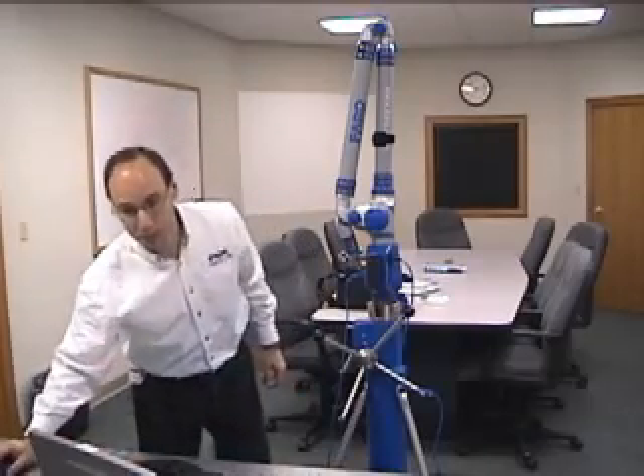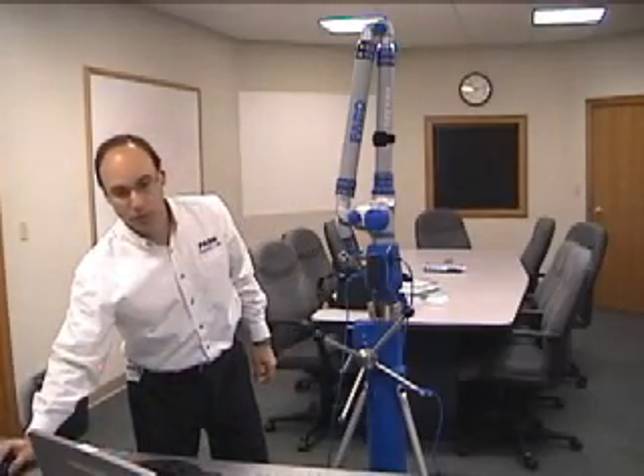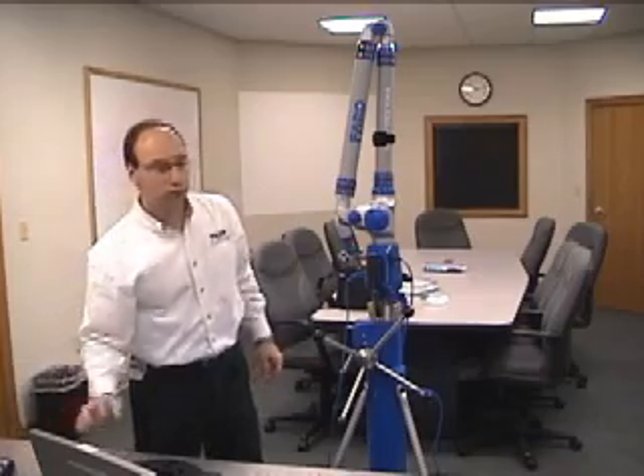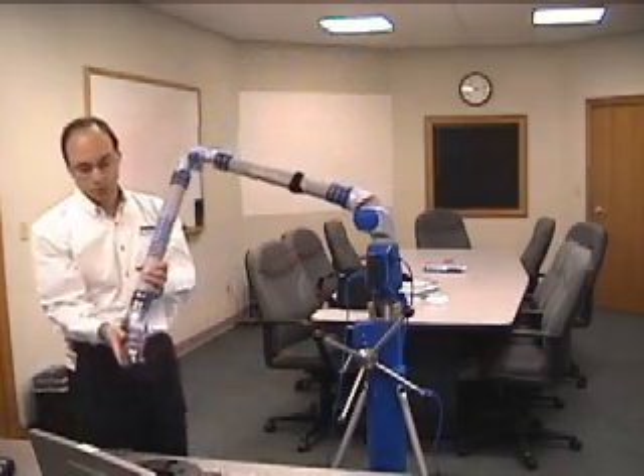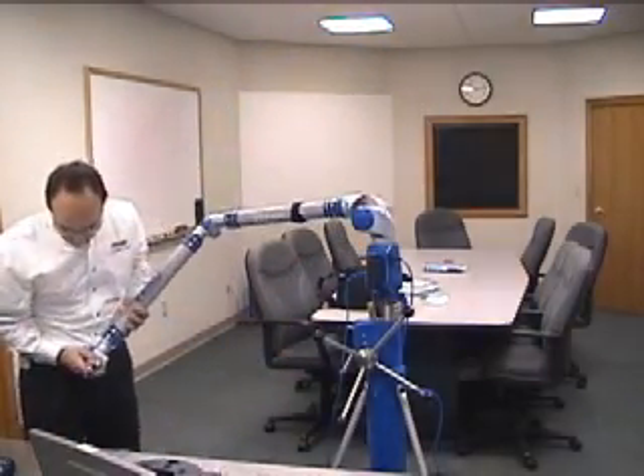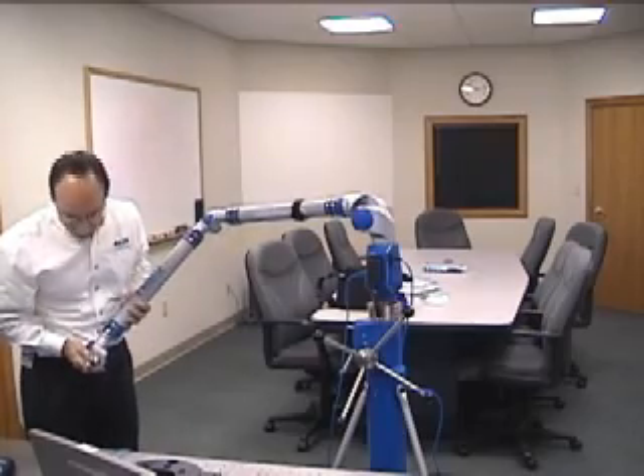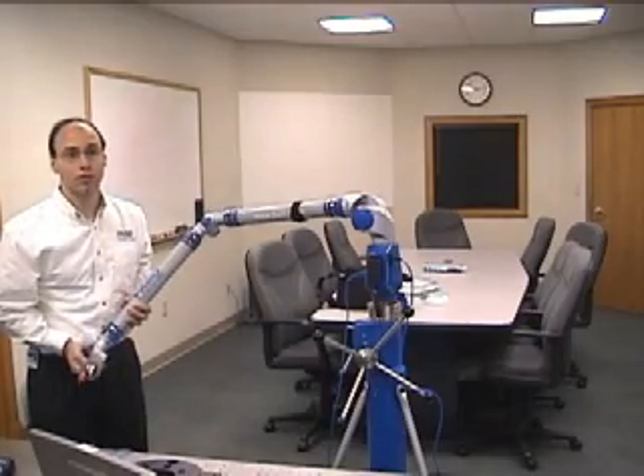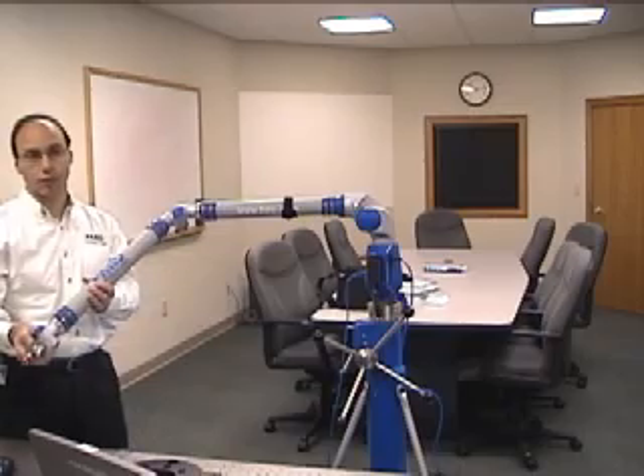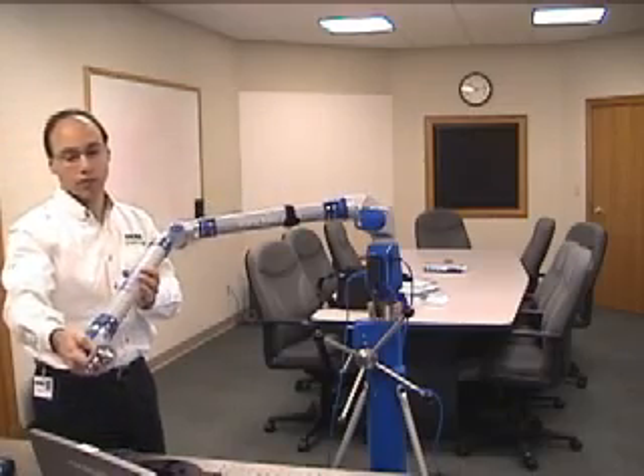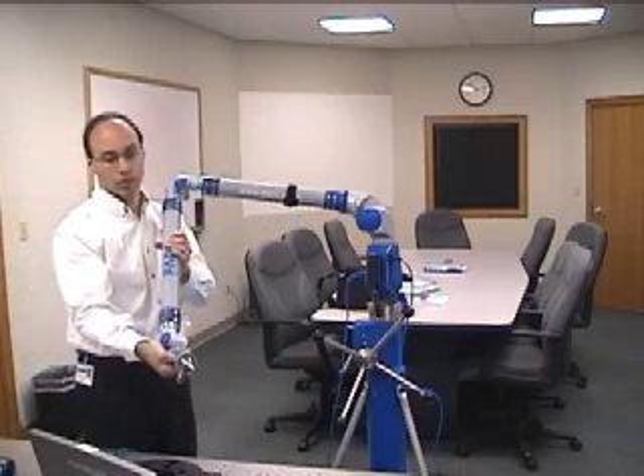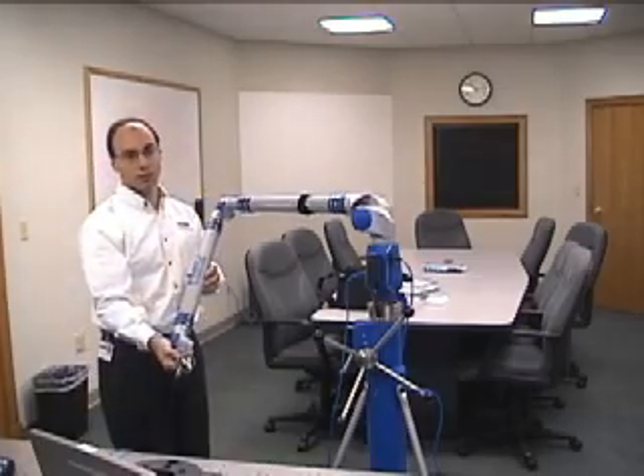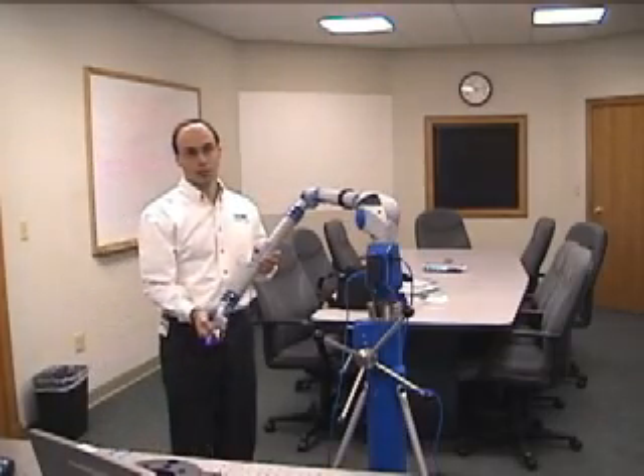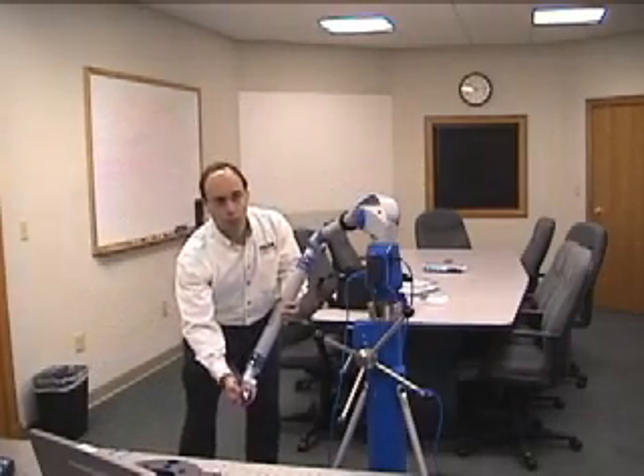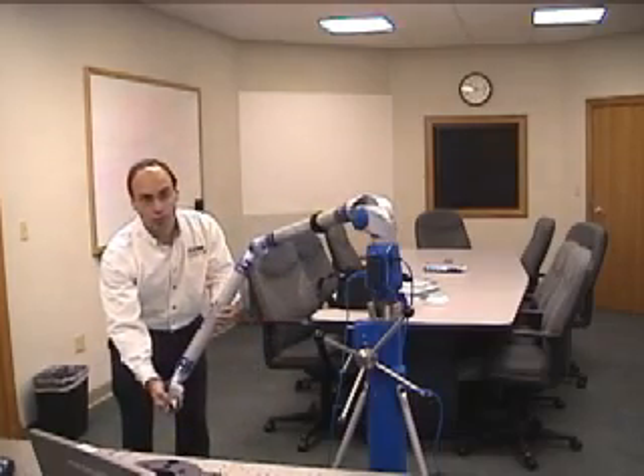Now we've moved the arm again. Click on the probe dialog and switch to arm. Then we take the arm and catch the beam again and begin taking points. It's good to take at least 12 points. After the fit is complete, the software will throw out any points that were unstable. So typically you might get 3/4 of your points in your fit.